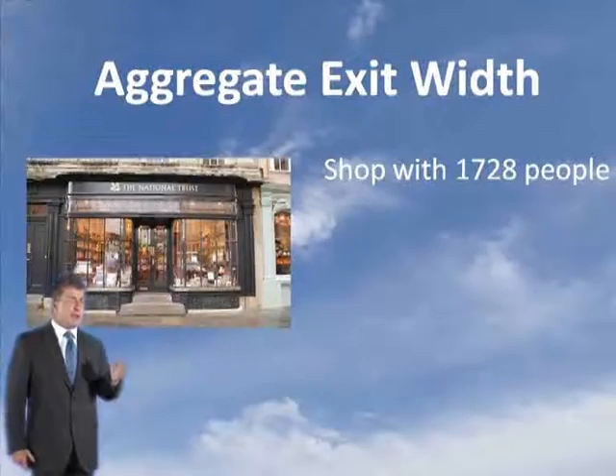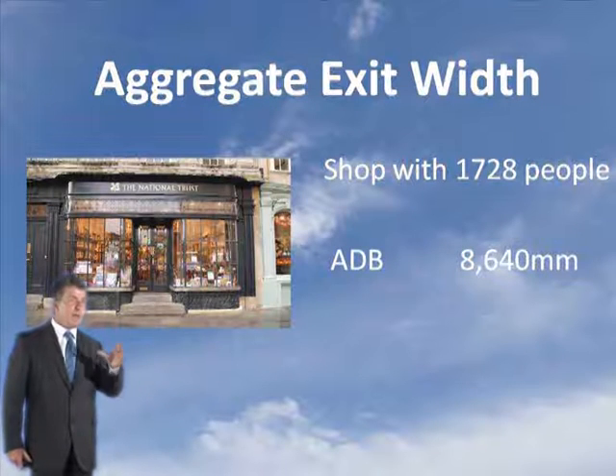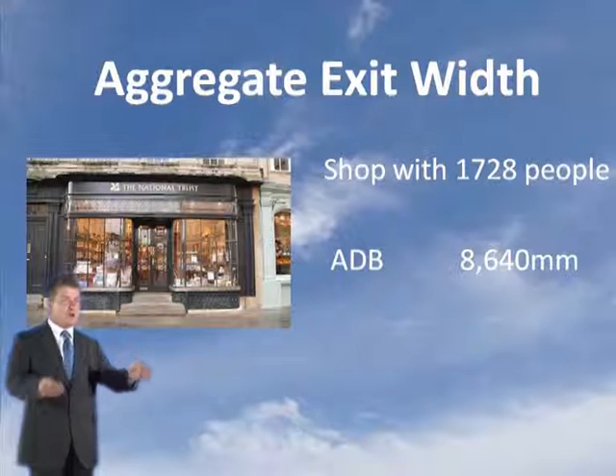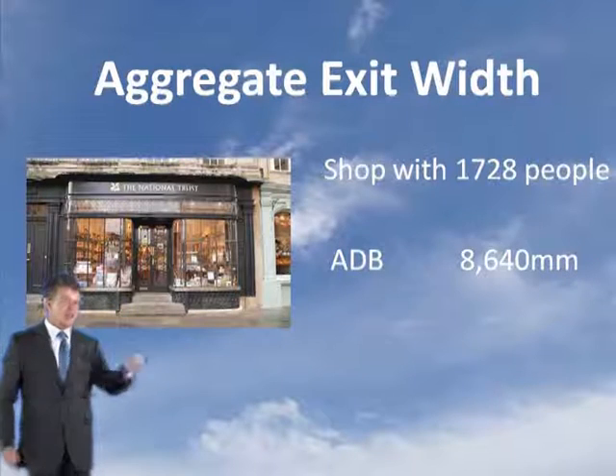Is BS 9999 just for larger developments? No. Any bar, any licensed premise, you want to look at this code because effectively what you're doing is demonstrating with the additional benefits that they can get out. And it's not compromising life safety, it's using fire engineered principles. What about a shop? A shop with 1,728 people in, ADB will require approximately 8,640 mil of available aggregate exit width to get them out.